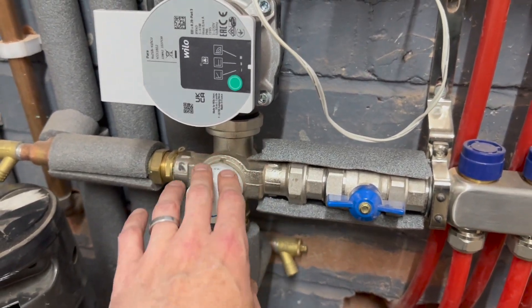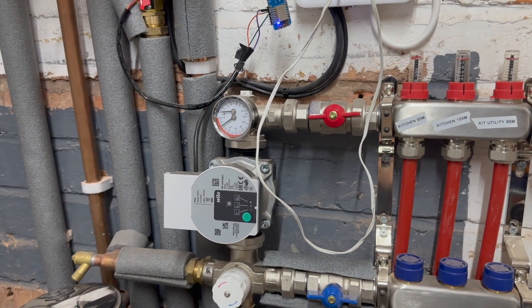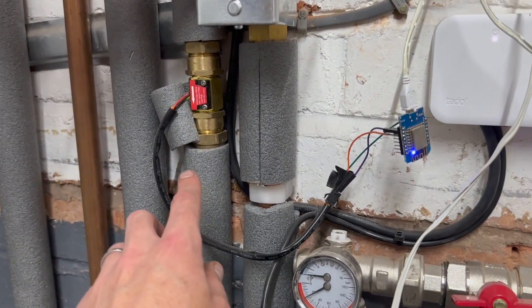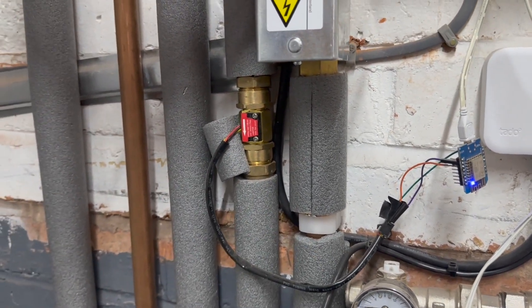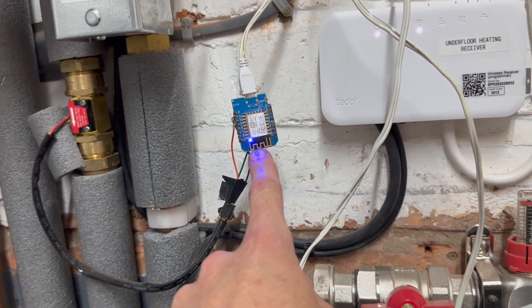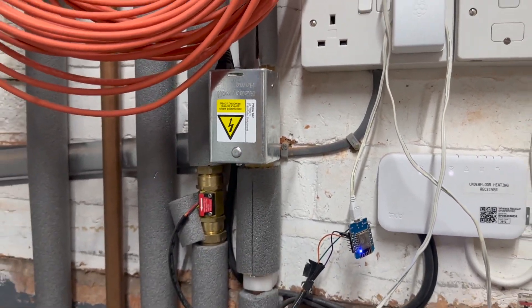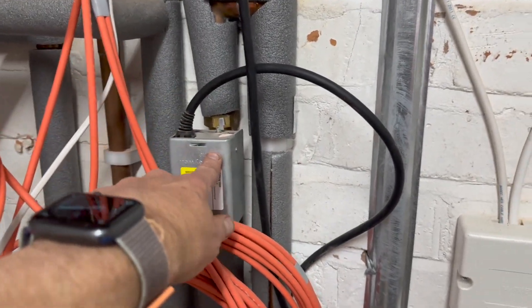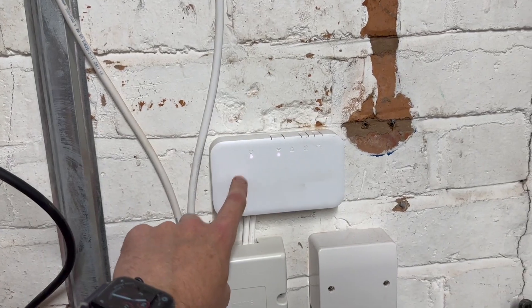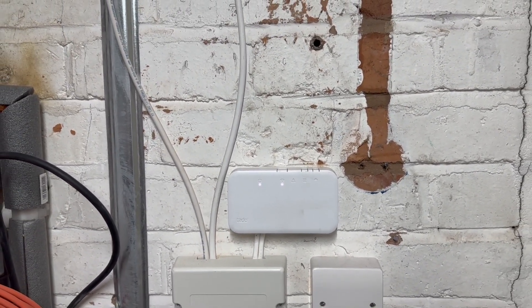I probably could have done away with the mixer completely, but I wanted to be sure that when it's very cold the boiler can go up to 50 — that's rare but I wanted it in place. Attached to the flow we also have a flow sensor — the noisiest flow sensor in the world — connected to an ESP8266, which provides that information via ESPHome into Home Assistant. There's a zone valve for the underfloor heating and a zone valve for the radiators, both operable independently. I am planning to ditch the Tado and install my own open source thermostat control system, which I'll cover in another video.